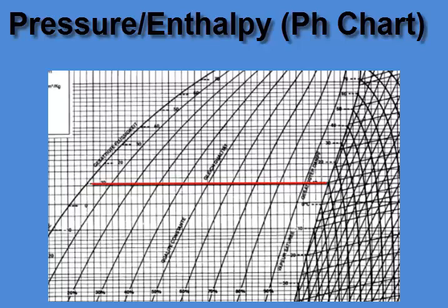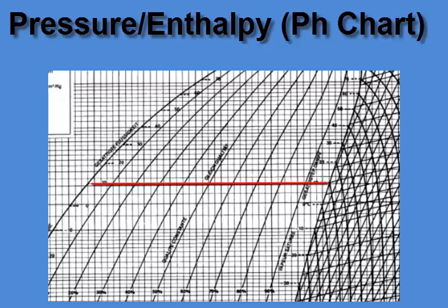So we will use the low pressure or the evaporator temperature to draw a horizontal line. As we see on this chart, the evaporator temperature was given as 10 degrees C, and therefore we have drawn a horizontal line that connects the 10 degrees C both on the left hand side and the right hand side under this bell-shaped curve, and we have the lower part of the cycle.